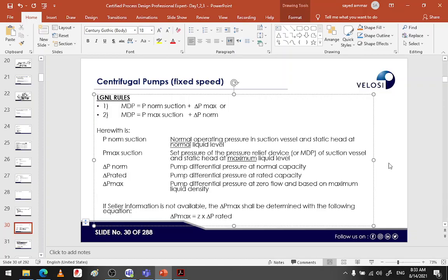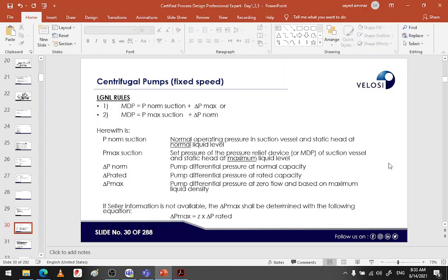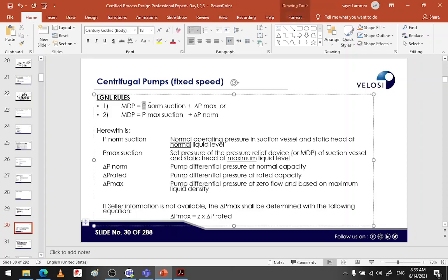The most important part at this time is that you understand that there is something called shutoff pressure. Shutoff pressure for any pump can be calculated from the normal suction pressure and the delta P maximum for the pump. This is the most important part at this point. Delta P maximum is the pump differential pressure at zero flow, based on the maximum liquid density.